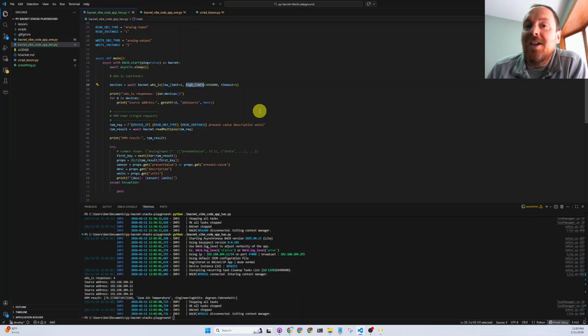It's not Ethernet based. BACnet can also run over that, but it's a very slow protocol. And if there's tons of devices on really old MSTP networks, doing lots of these can really bog down those networks. With BACnet over IP, you probably wouldn't have to worry about it very much.